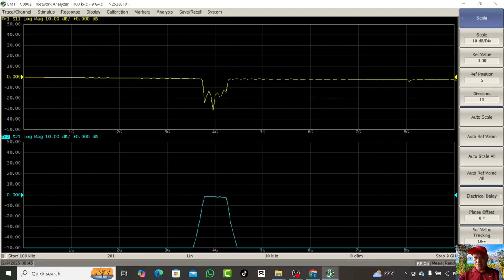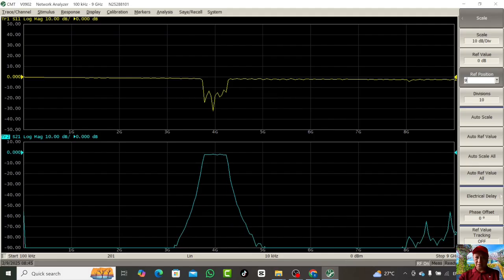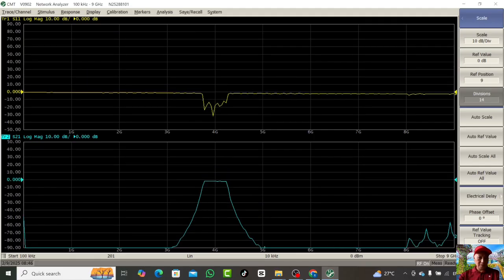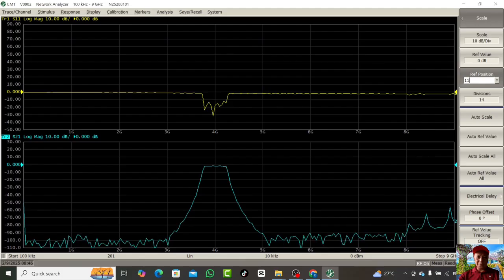Okay, the scale is here. So the division is 10. And then the reference position, I think I should change the reference position. Here it is 5, so if I increase it to 6, yes, okay, I can see the noise floor, but you can see the noise floor is still below here, and I don't think I can get enough with the reference position alone. So I should change the scale of this division, for example, to 15. Okay, so then I can increase it. Yeah, so you see, we can see the noise floor here.